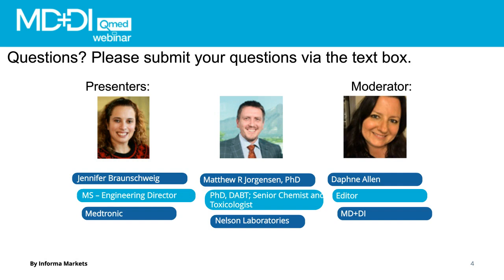Yeah, that's a good question. So there are a lot of devices out there, especially PVC devices, that have CMRs above 0.1%. So PVC commonly has a plasticizer in it, diethylhexyl phthalate, DEHP, and it's often at concentrations greater than 0.1% by weight. So in that situation, the GSPR 10.4 simply says that the presence of that compound needs to be justified.